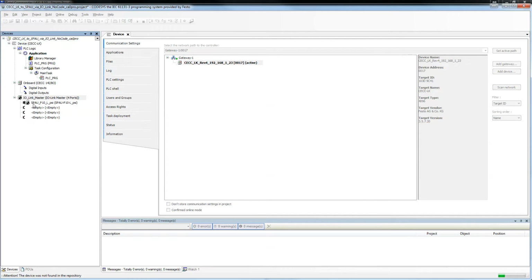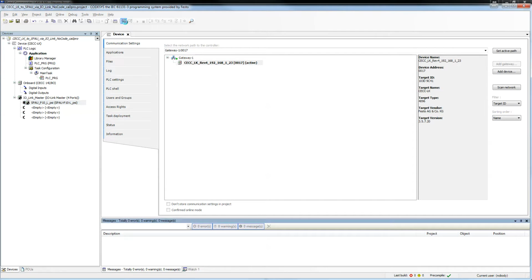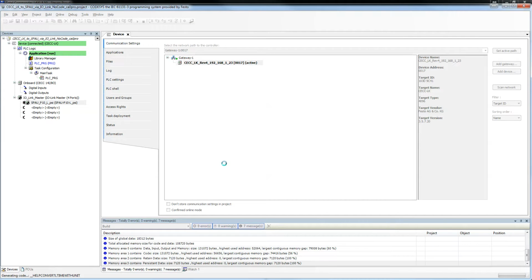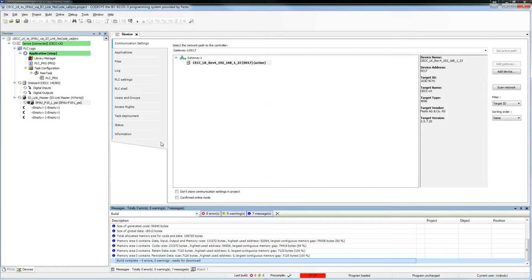So the device is actually connected to port number one. Select it, copy. Now, of course, the EDS or the IODD file has to be installed previously to recognize this properly. So save it, download, yes. Put it in run mode, F5, it's in run mode now.